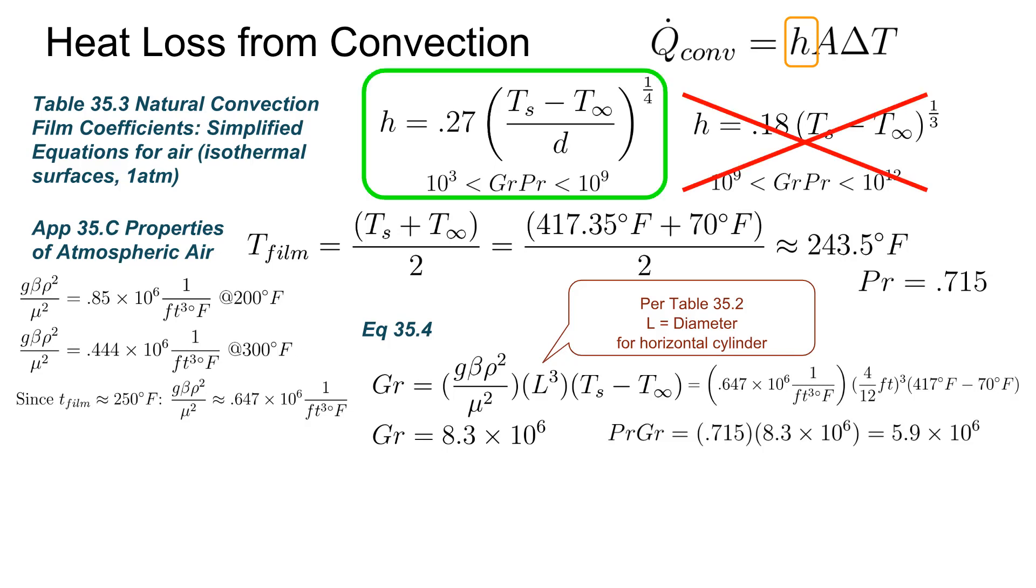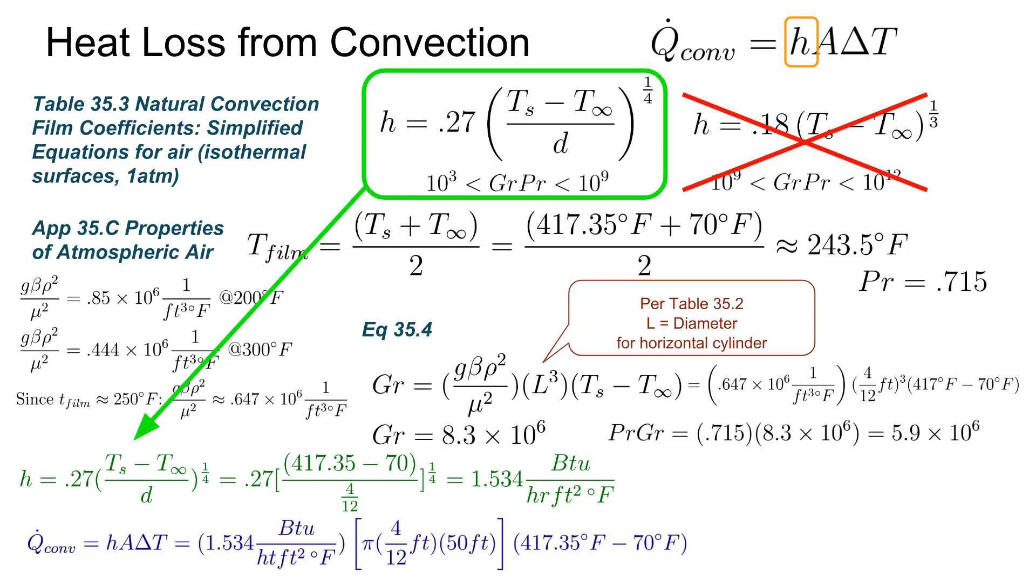We can plug in for the temperatures and diameter, all of which are known, and we get a film coefficient of about one and a half BTU per hour foot squared degrees F. And finally we can find the heat loss from convection, which is the one and a half times the area, which as before is the surface area of the pipe, pi dl, and all of that times the delta T. And we get a heat loss of 27,900 BTUs per hour, which is actually a bit less than the radiation heat loss, but both are similar contributions.